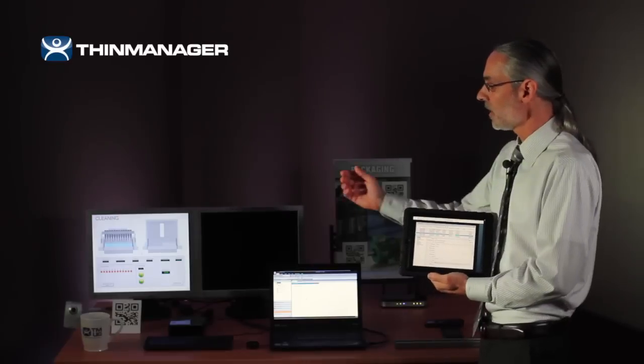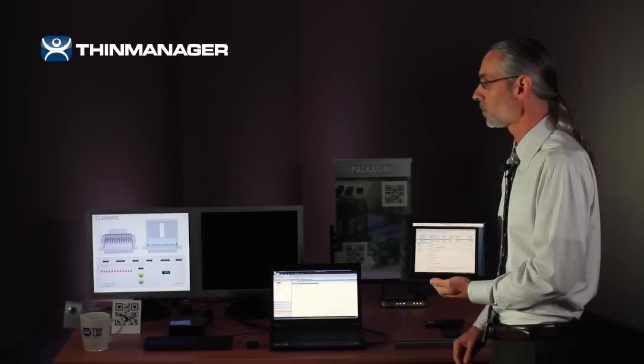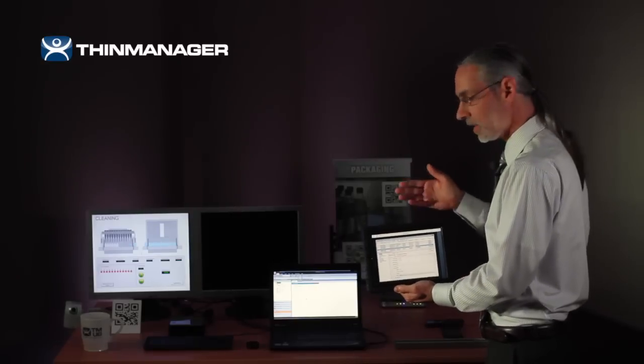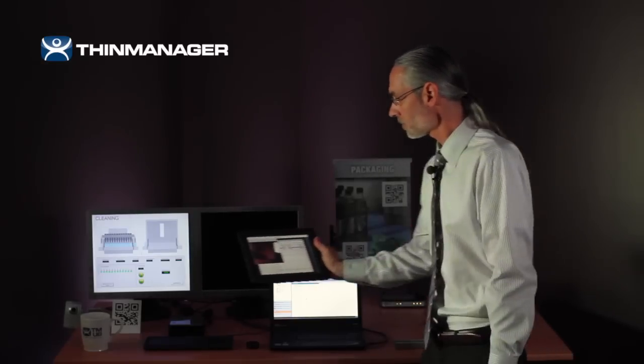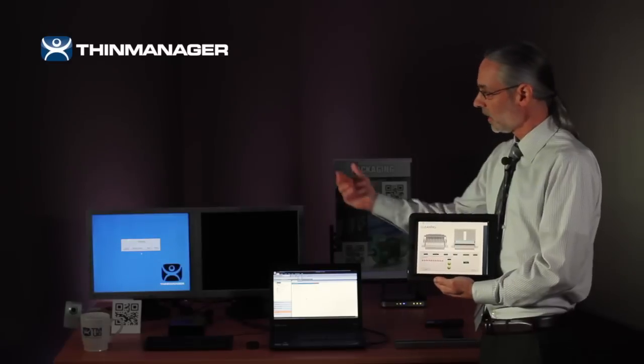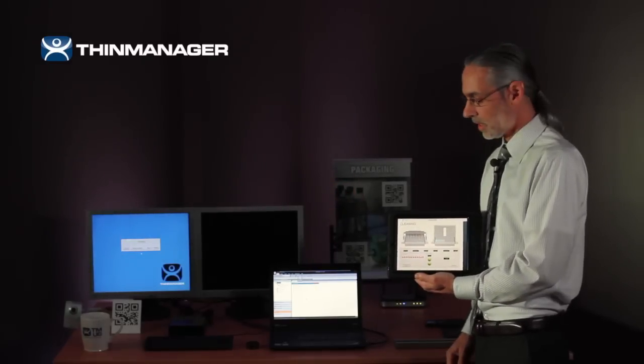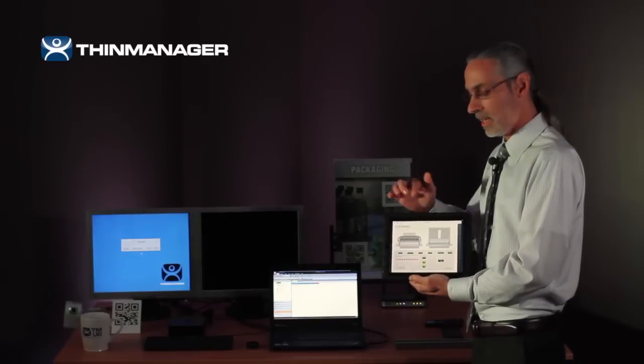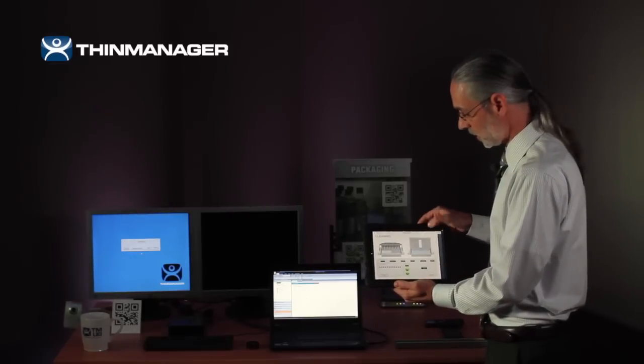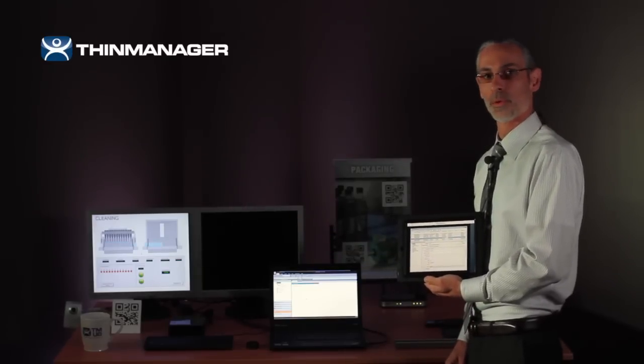In this case, my maintenance person needs to interact with the HMI that's attached to the tethered thin client terminal in the work environment. Instead of having to be at that terminal to interact with the HMI, we're going to use force transfer to allow the maintenance person to take the HMI and use it on the device. Now that I'm logged in, I hit the scan ID button, go over to my QR code, and when I scan it you'll see that immediately the application is taken away from the tethered terminal and given to the iPad. I can move within my environment, interact with the application, and when I'm through I simply hit the leave button to return the HMI to the tethered terminal so the operator can continue their work. That's force transfer.